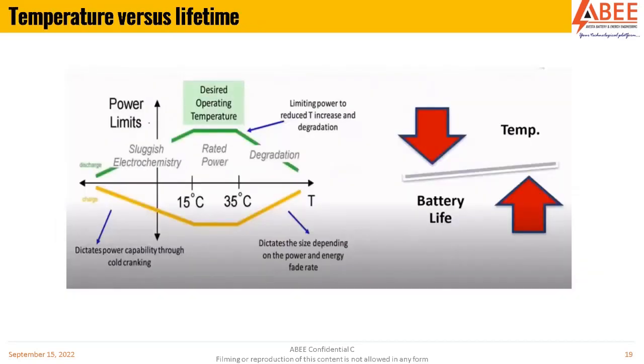Thermal management is very important. Most home storage or even industrial applications are still air-cooled, either passively or actively. But to keep the best performance for lithium-ion batteries—NMC, NCA, or LFP—the temperature window should be in the range of 15 to 35 degrees. Above 35 degrees, the electrolyte inside the cell becomes unstable and can create gases, as demonstrated by the pouch cell, and lifetime will decrease. If you often go below 0 degrees, you'll destroy your battery due to lithium plating, and close to 0 degrees, performance will drop.